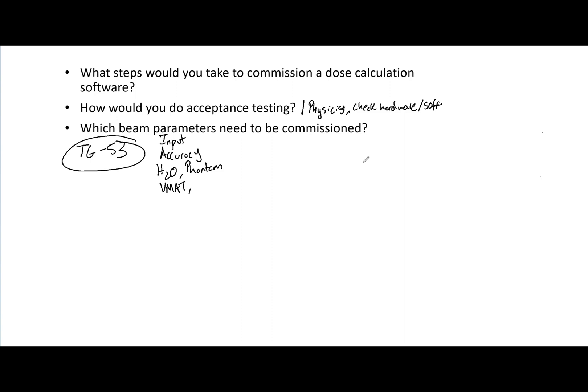Typically this can be done with the vendor — they normally walk you through it — but it could also be done by yourself if you're familiar with it and don't need the vendor. In my clinic, the vendor came to me, showed me all the paperwork, showed me what the expected accuracies should be. We then proved that, and I had to sign papers saying I was there for the acceptance testing and agreed with what they said.